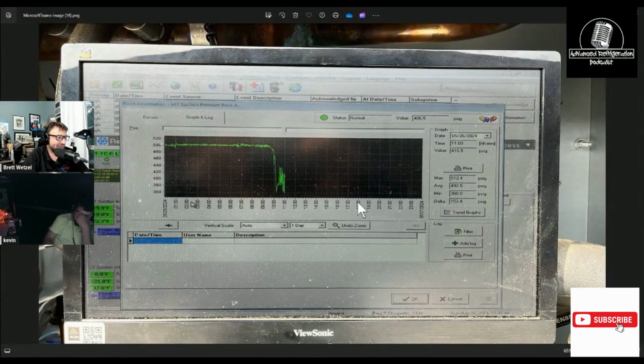It's fine. So you can see, like, around that same time it failed, right? So I hear him beating on the valve. I hear tink, tink. I'm like, what are you doing? He's like, nothing. I'm like, you're beating on that valve to try to get it to feed. It's, no. I was like, you need to take it apart. But apparently on this rack, there was no shut off where it connects for the BGV. There's no isolation. No, there was no little itty bitty valve. So yeah. So anyway, so you could see suction pressure, superheat, suction pressure, superheat.